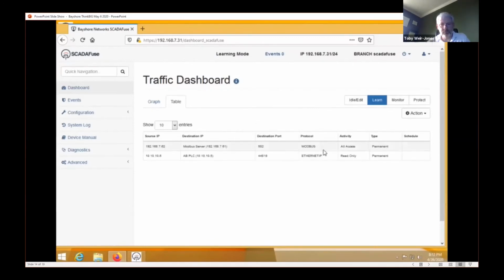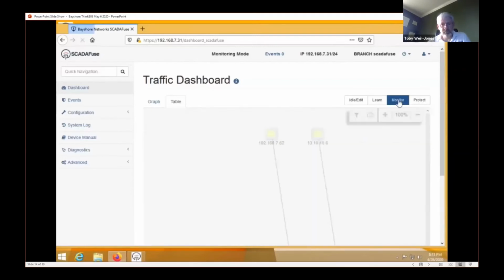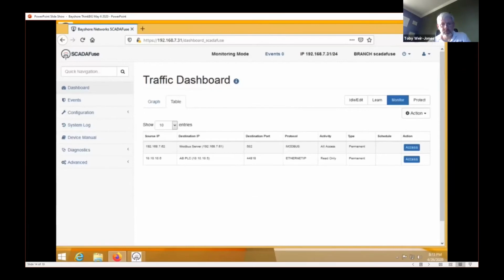What we can see here is that it's observed some Modbus activity, and importantly, some Ethernet IP activity, but only in a read-only set of function codes. If we know that source for the Ethernet IP needs to generate additional write-type operations, we can add that in one of two ways.